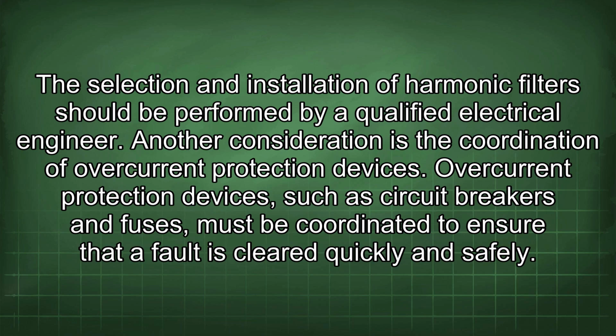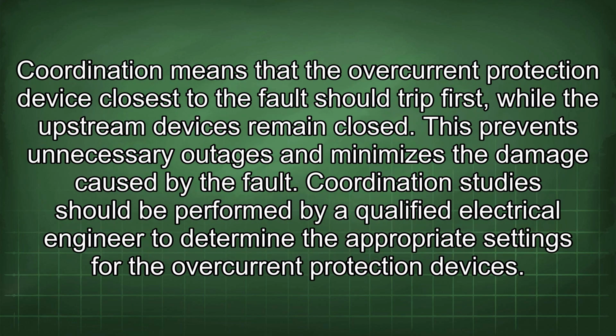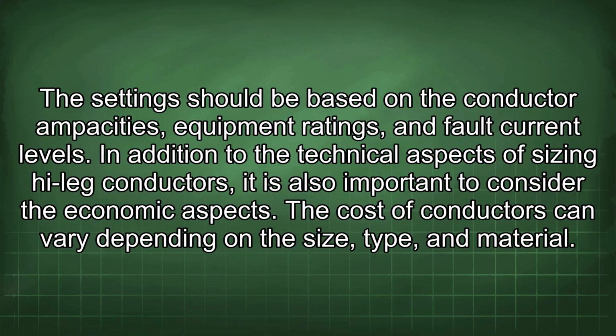Another consideration is the coordination of overcurrent protection devices. Overcurrent protection devices, such as circuit breakers and fuses, must be coordinated to ensure that a fault is cleared quickly and safely. Coordination means that the overcurrent protection device closest to the fault should trip first, while the upstream devices remain closed. This prevents unnecessary outages and minimizes the damage caused by the fault. Coordination studies should be performed by a qualified electrical engineer to determine the appropriate settings for the overcurrent protection devices. The settings should be based on the conductor ampacities, equipment ratings, and fault current levels.